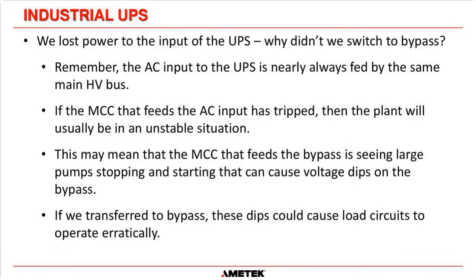But you've got to remember, if you lose power to the AC input to the UPS, it's nearly always fed by the same main HV bus back at the MCC. And now, if the MCC that feeds the AC input has tripped, then usually the plant will be going through an unstable situation. Because you've got to remember, if that MCC that feeds the AC input has tripped, there are many other things related to that MCC that are going to have a domino effect in the plant.